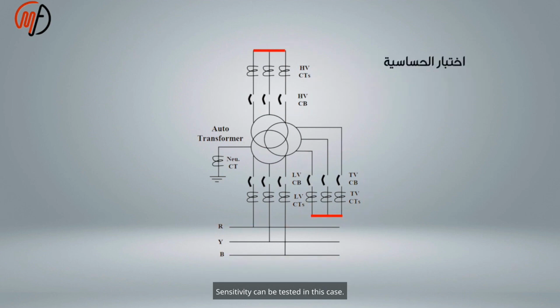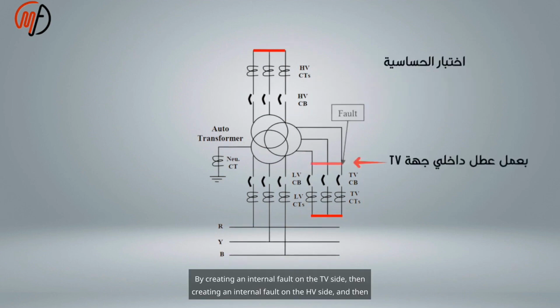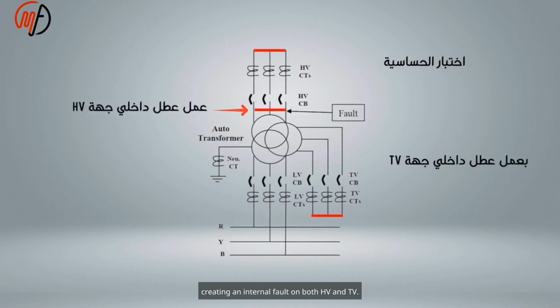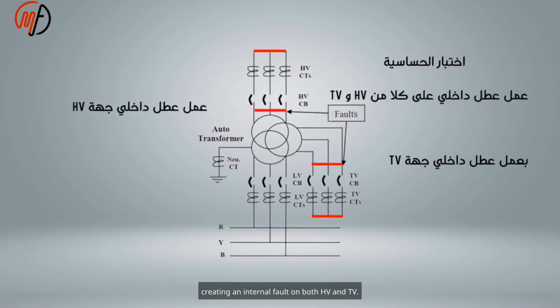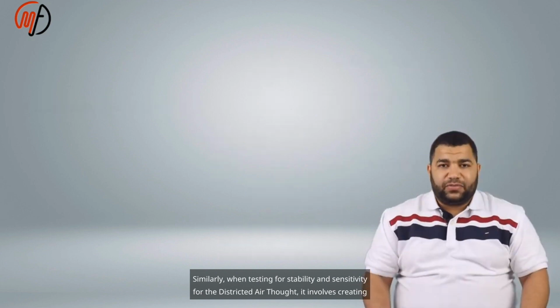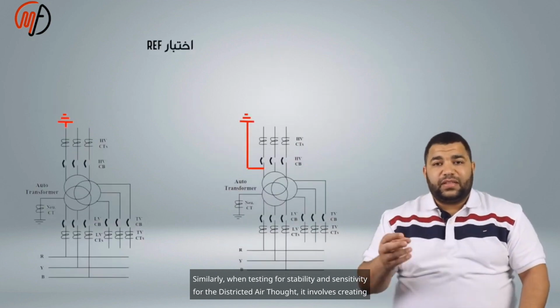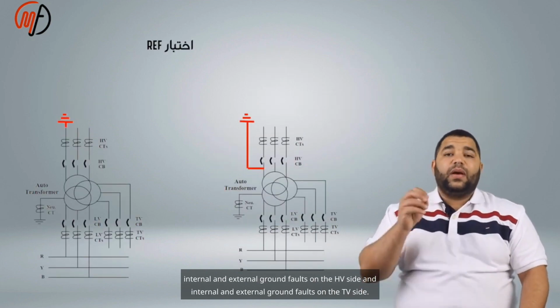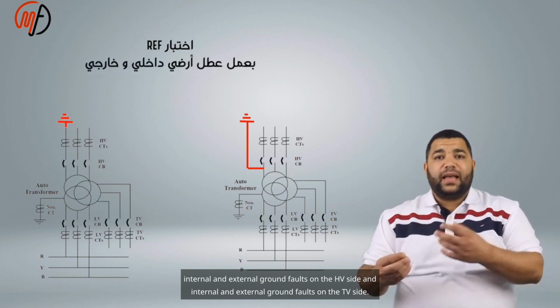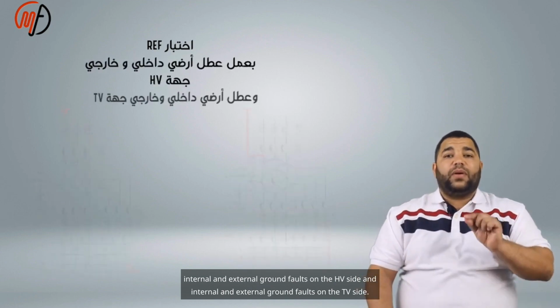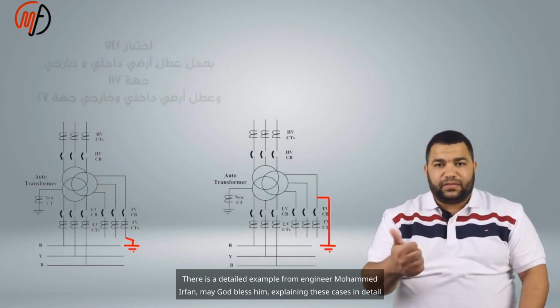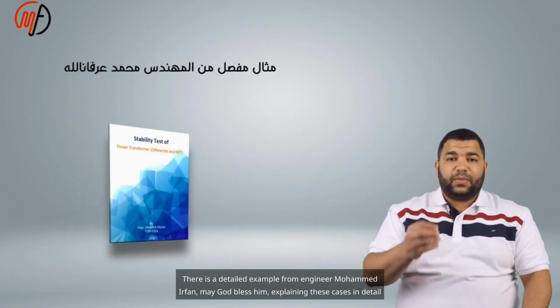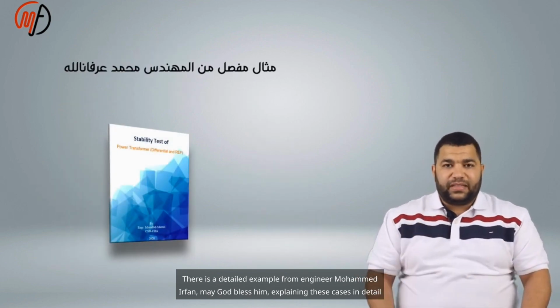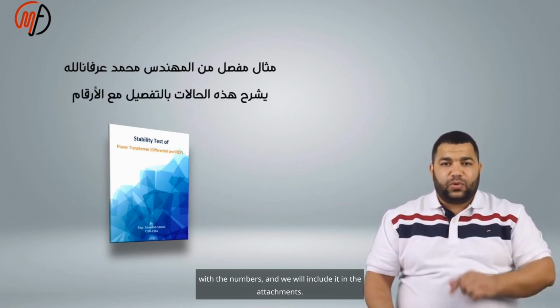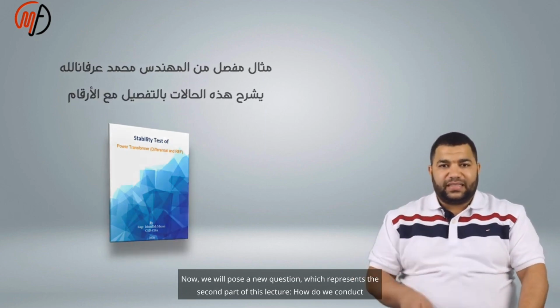Sensitivity can be tested in this case by creating an internal fault on the TV side, then creating an internal fault on the HV side, and then creating an internal fault on both HV and TV. Similarly, when testing for stability and sensitivity for the restricted earth fault, it involves creating internal and external ground faults on the HV side and internal and external ground faults on the TV side. There is a detailed example from engineer Mohammed Irfan, may God bless him, explaining these cases in detail with the numbers, and we will include it in the attachments.